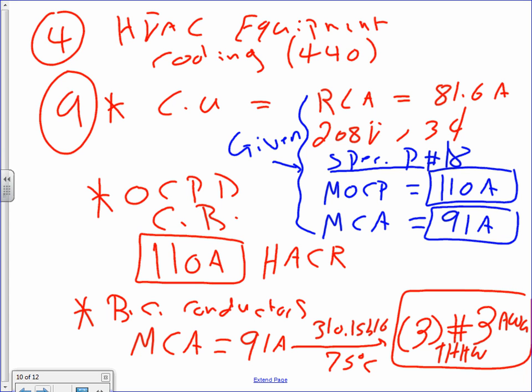The spec that came with the equipment, all these descriptions of mechanical equipment, is right on the nameplate. Then from there, you have no option other than using the overcurrent protection device and using the minimum circuit ampacity for sizing the conductors. Can I have a thumbs up, Chad? We fully understand that? We didn't have to worry about 1.25 here? No, not with minimum circuit ampacity, no.